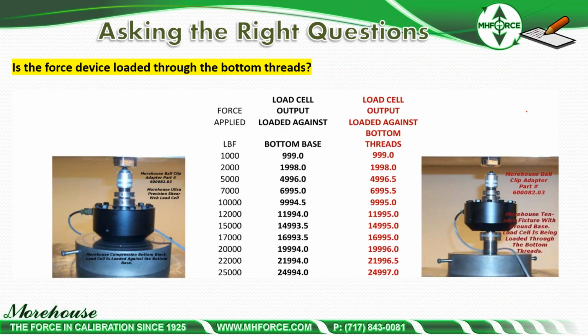How about loaded through the bottom threads? Our competitors like to set everything up on one machine, they do a calibration in 5 to 10 minutes, get everything done, compression, tension, woohoo. Not that that's a major issue. However, the major issue here is if they're loading it through this way, loaded against bottom threads, and you're using it this way, you're going to have about a 0.01% error. Right here, it's 3 pounds out of 25,000. You're going to have it.